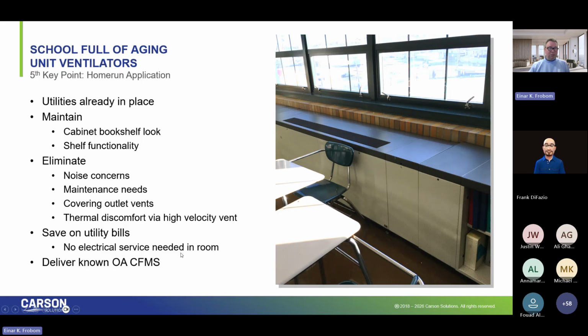We're going to save on energy and utility costs, and we're going to deliver the known amount of outside air that's so critical. How many times do these unit vent systems get their outside air damper shut off because they don't want to freeze the coil, they don't want diesel fumes coming in, they don't want insects, dust, grass clippings, etc.? And that's what happens, because it's an easier fix than dealing with that damper being open.